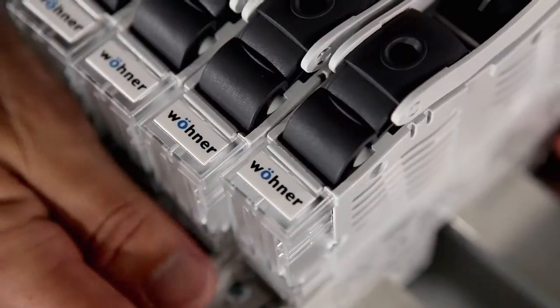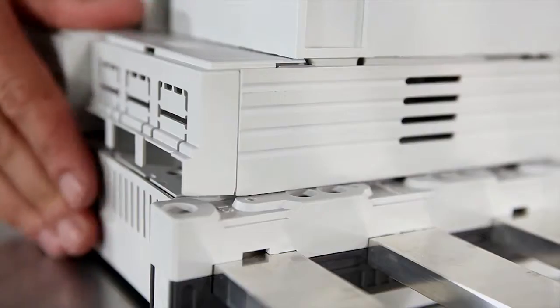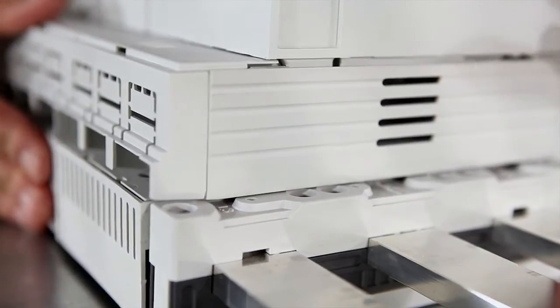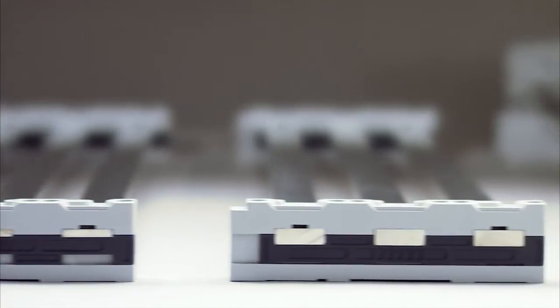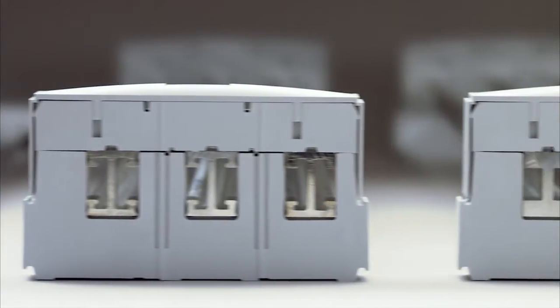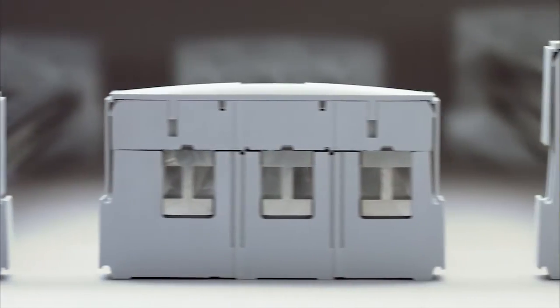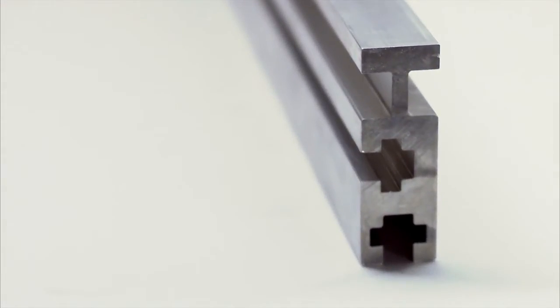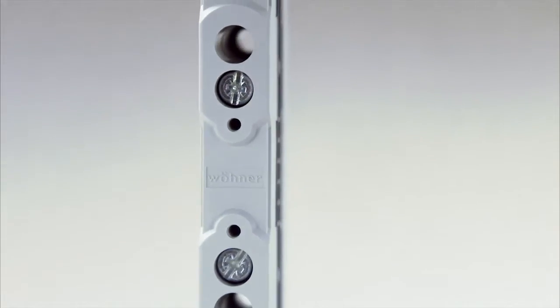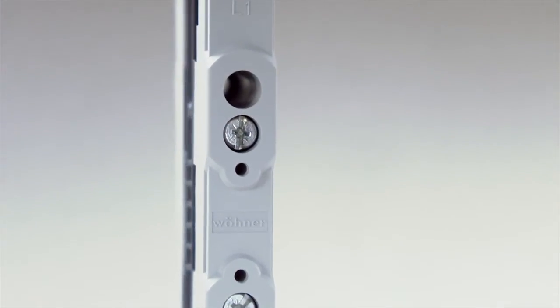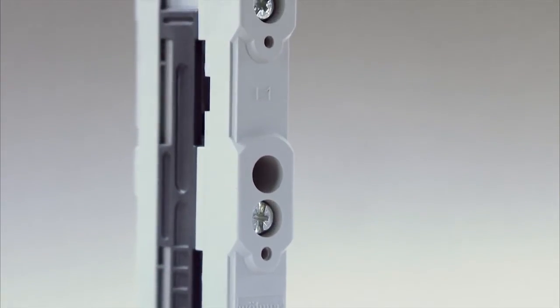The capacity of bus bar systems is increasing all the time and they can be optimally adapted to the respective scope of application. They are based on commercially available flat bus bars in different cross sections up to a maximum of 30 by 10 millimeters. These are supplemented by Wöhner special profiles such as the double T, triple T, and TCC profile for high power requirements. This enables currents of up to 2500 A to be carried safely.